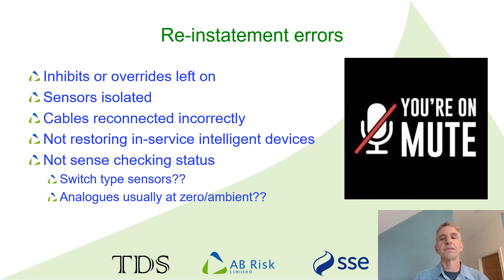The ability to sense-check the SIF is really useful, but works well only if the SIF uses an analogue sensor and other analogue devices are installed at a similar part of the process. Switch-type sensors are a well-known example — they're either on or off. The trouble is you have no indication during normal operation whether they're working or not. Normally we'd say an analogue sensor avoids that problem, but only if it sees some fluctuation during normal operation. If the process is normally at zero or ambient, even an analogue device isn't going to give us that normal indication that the system is working.